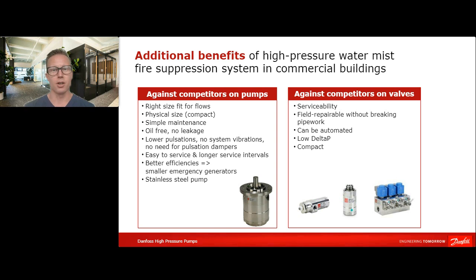Due to the high number of pistons inside, the pulsations are very low and there's no need for pulsation dampeners also. In fact, the whole installation is quite simple. It just consists of an electric motor, a coupling and a bell housing, and then directly mounted with a pump. And finally, these pumps have a very high efficiency, and especially here when we are talking about firefighting systems, the size of the emergency generators is important.